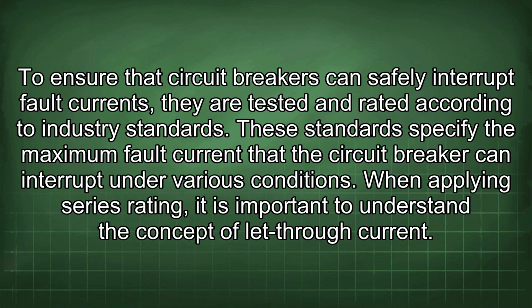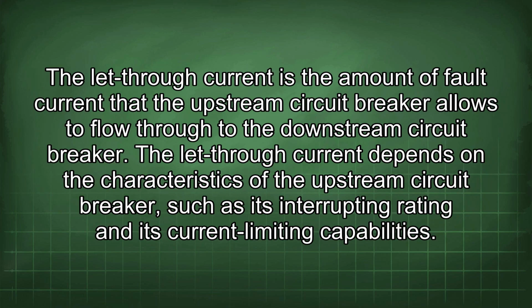To ensure that circuit breakers can safely interrupt fault currents, they are tested and rated according to industry standards. These standards specify the maximum fault current that the circuit breaker can interrupt under various conditions. When applying series rating, it is important to understand the concept of let-through current.